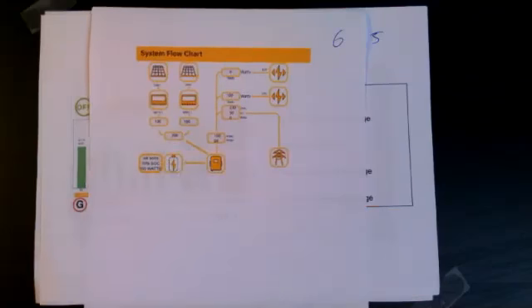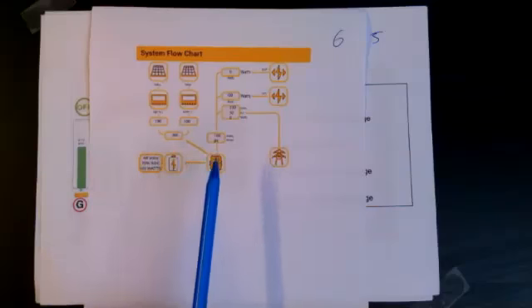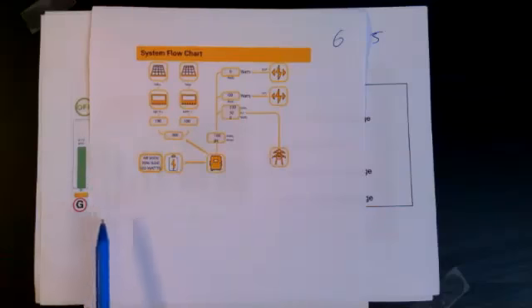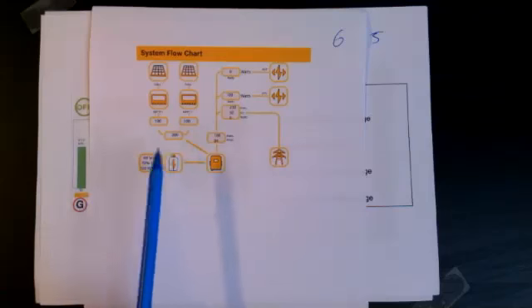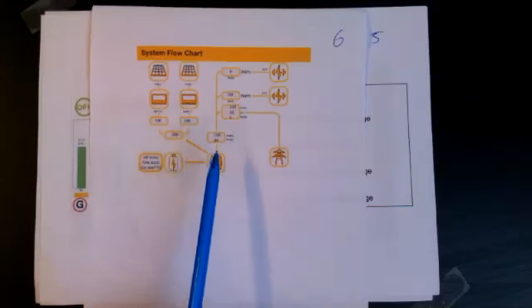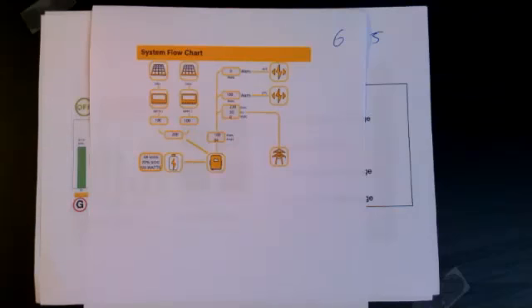And so a lot of people do, because they want the battery for load shedding as an emergency. So they put the solar first, go to the battery, and secondly, go to the load. And if that's the case, you will draw power off the grid. Or you can have the power go into the load first and the surplus power go into the battery. And you can choose what you want to do with it.